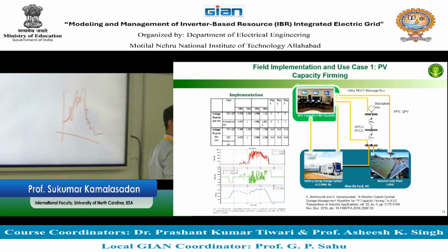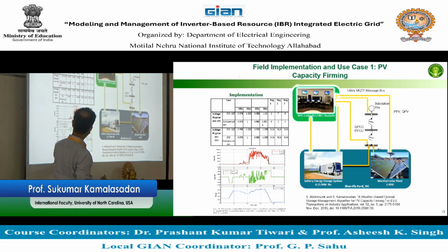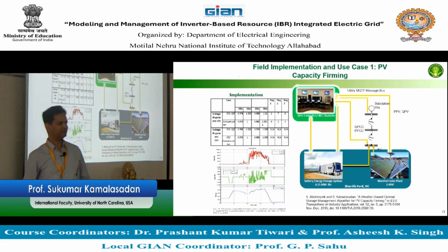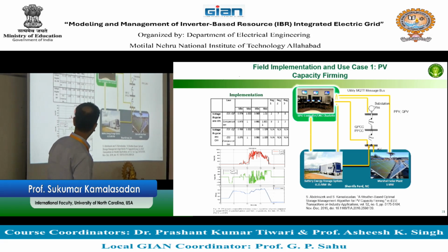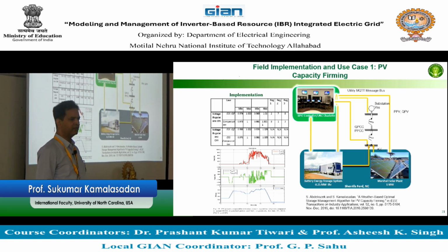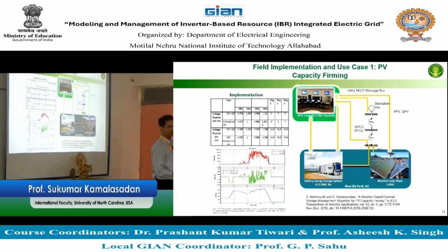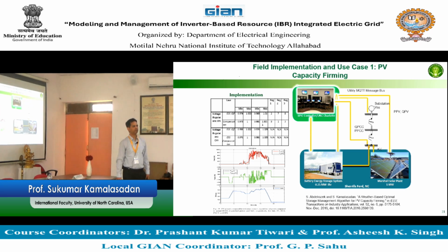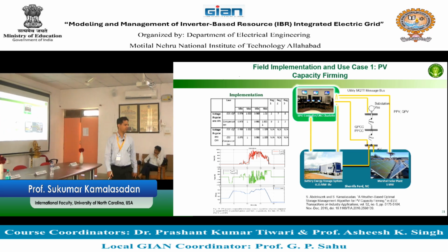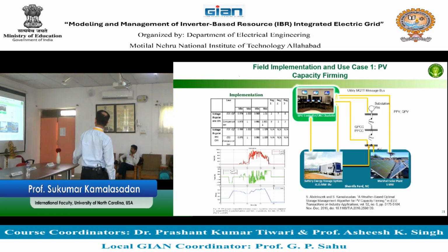called firming. So in here you see this black line is a smooth line as much as it can be, not very smooth, but the best smooth line as opposed to this red line, and this is the arbitrage point. Our utility wanted to have a smooth line without the energy forecast. So we are smoothing. The time limit is 1 day. So this is night, this is 9 o'clock, and this goes back here.